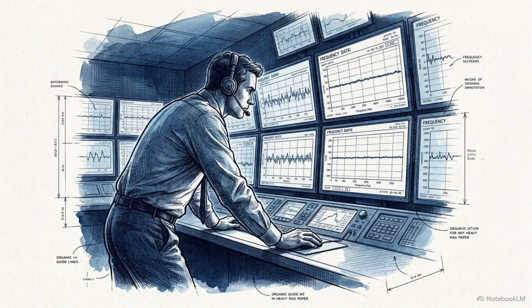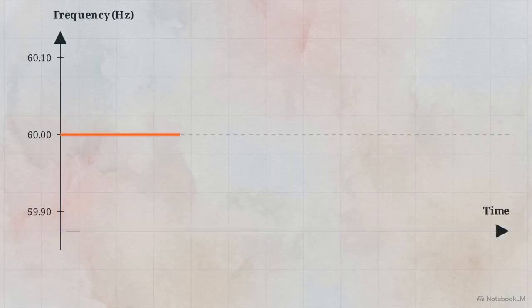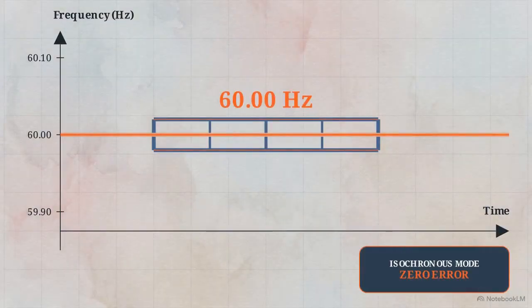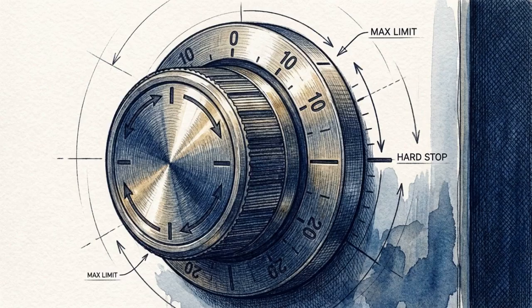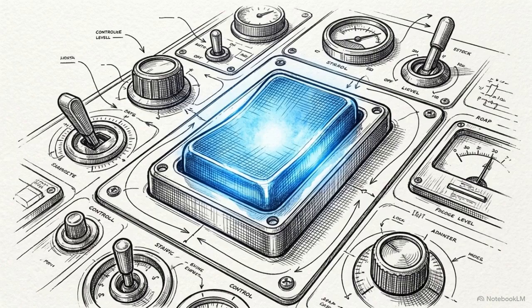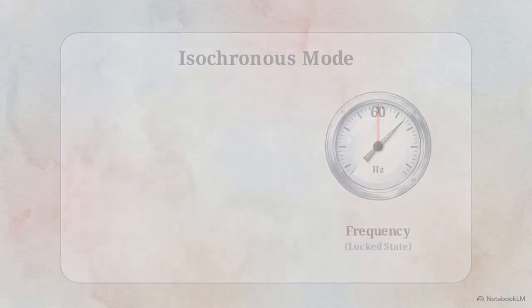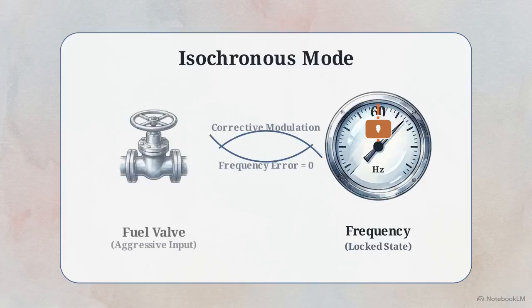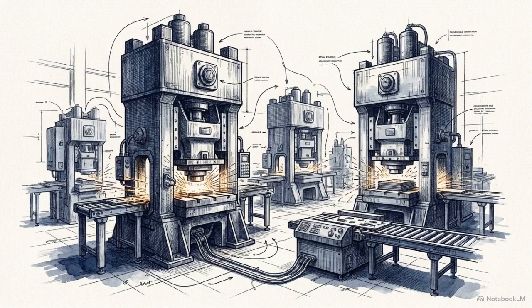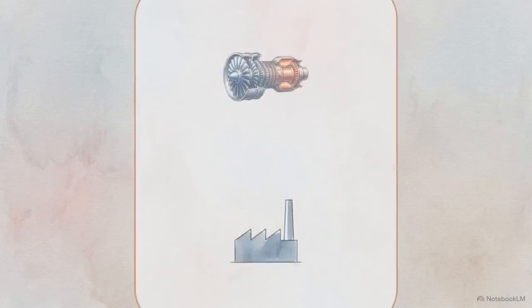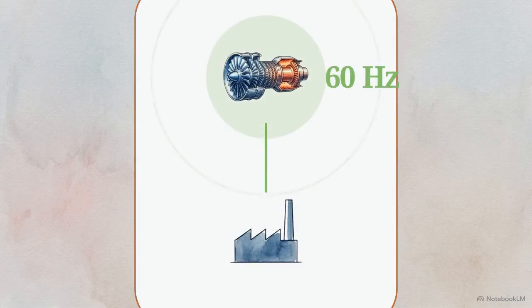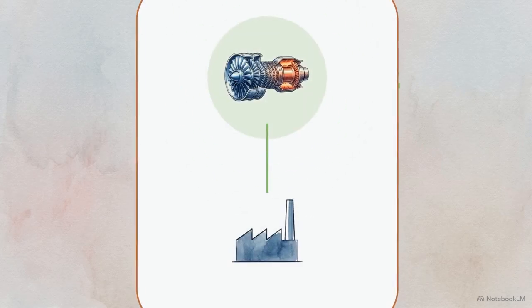To engineers tasked with keeping that frequency stable, the logical approach seems obvious. You configure the turbine's control system to hold that 60 Hz target perfectly, correcting for any deviation with zero allowable error. This specific governor command is called Isochronous mode. In this state, the turbine rigidly holds exactly 60 Hz, constantly adding or cutting fuel to correct for any frequency dip or surge, regardless of how much physical load is applied to the generator. For a single machine running in isolated island mode, this rigid, zero-error control works perfectly.